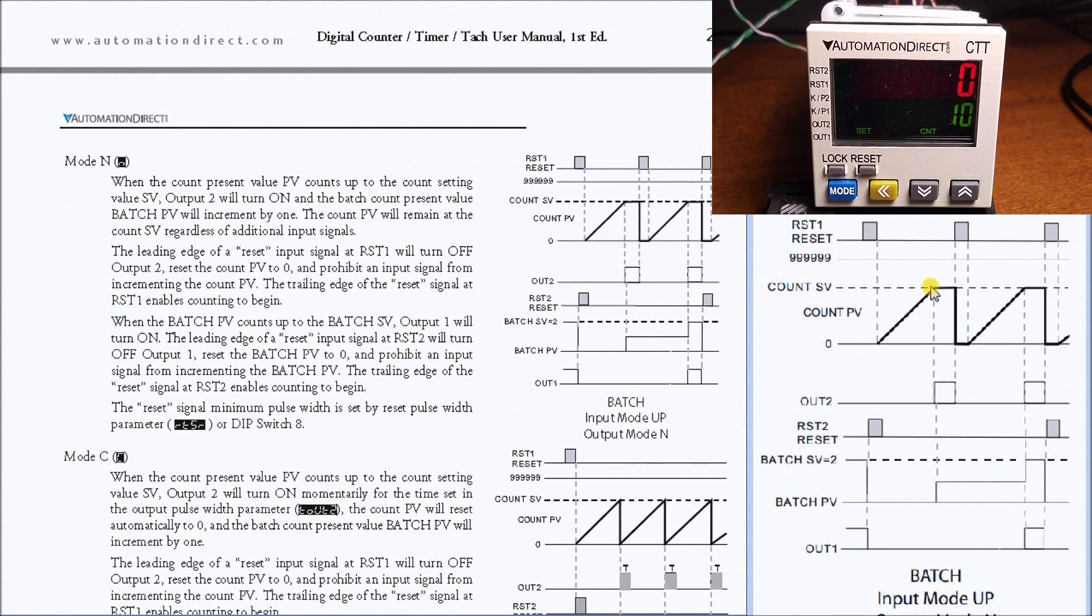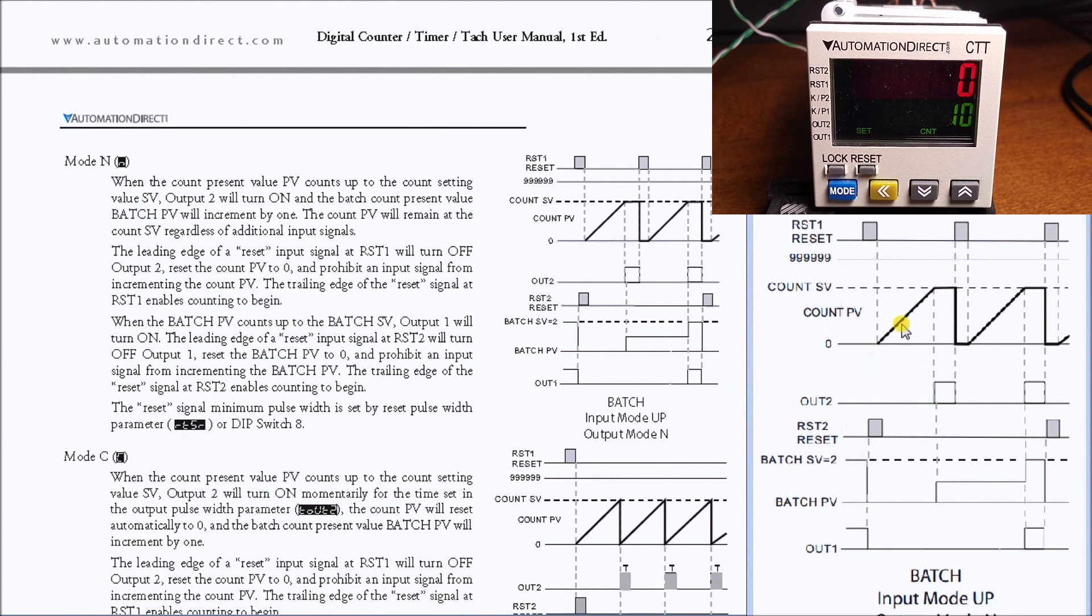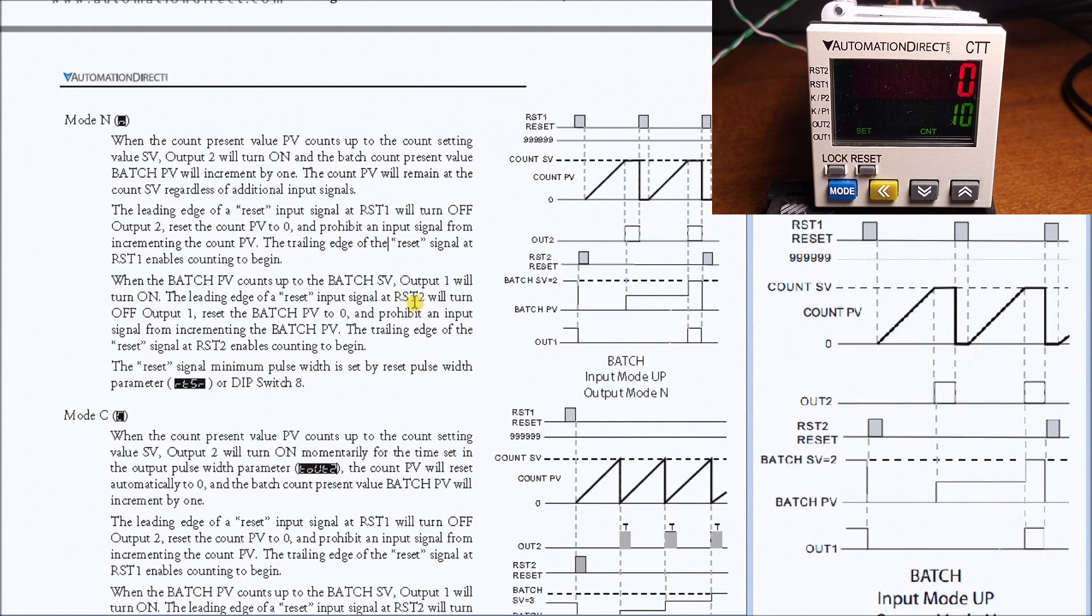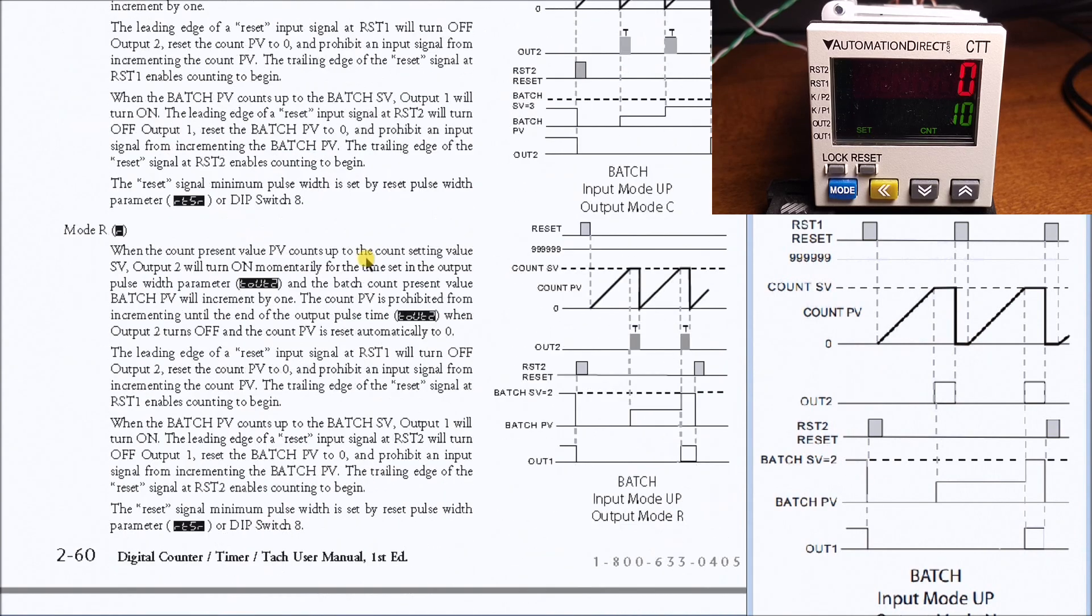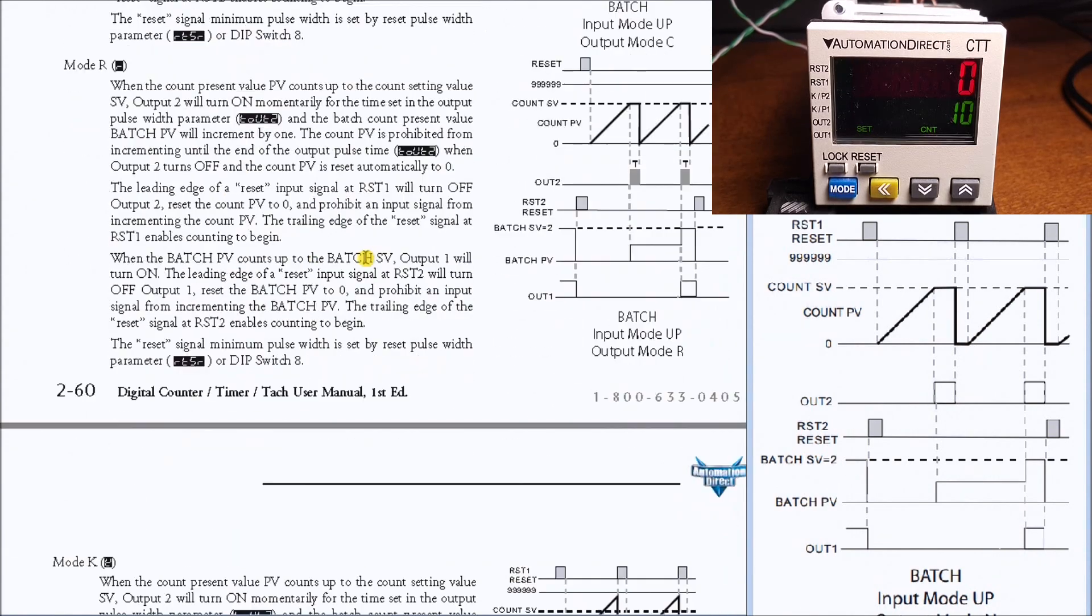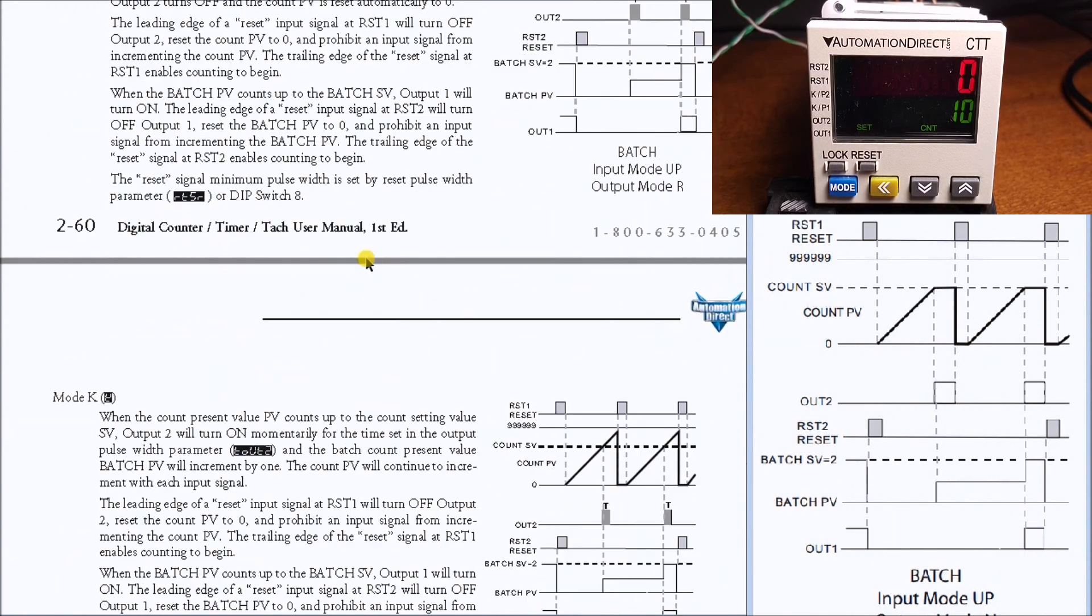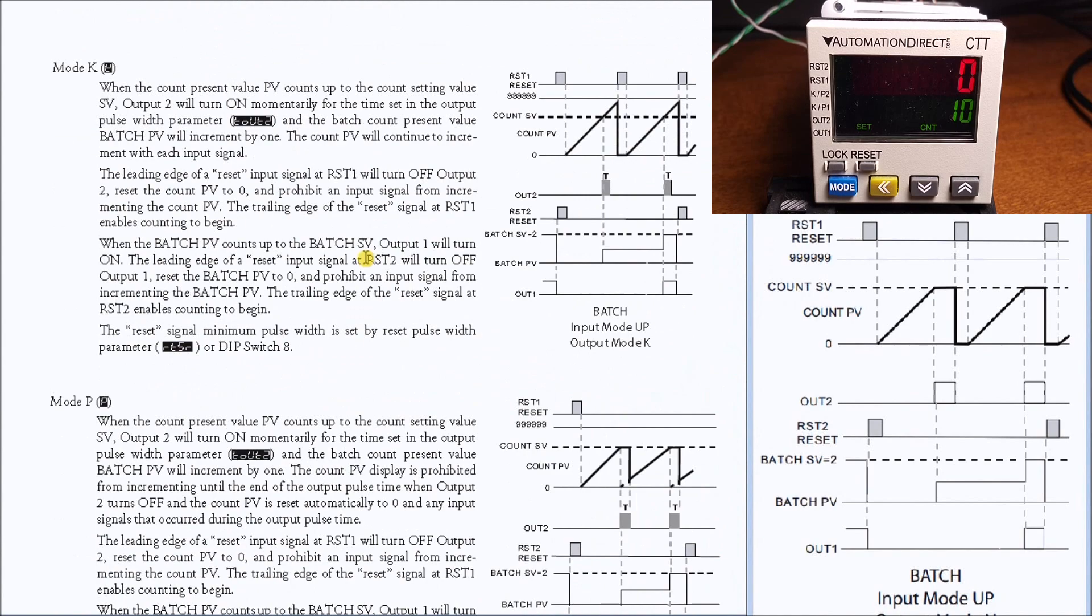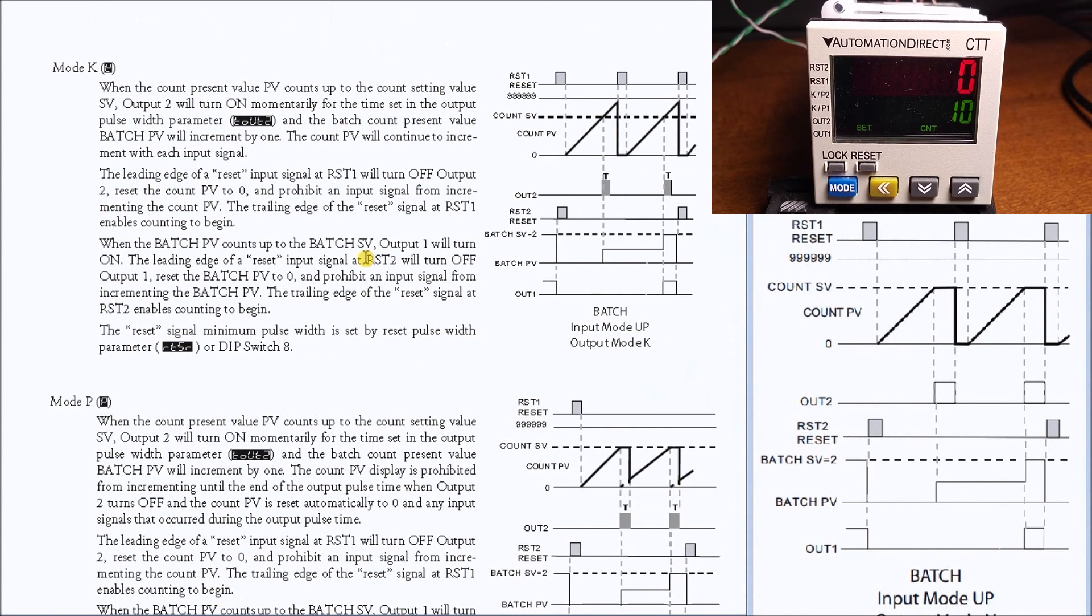Every time we count to the full count value we will increment one on the batch until our set value for the batches is on, and then the other output will turn on. So there are two outputs there. Looking back in the manual, that's the mode we want to program and we have different modes that we can actually operate in, so we choose the mode to the applications that we're trying to accomplish.